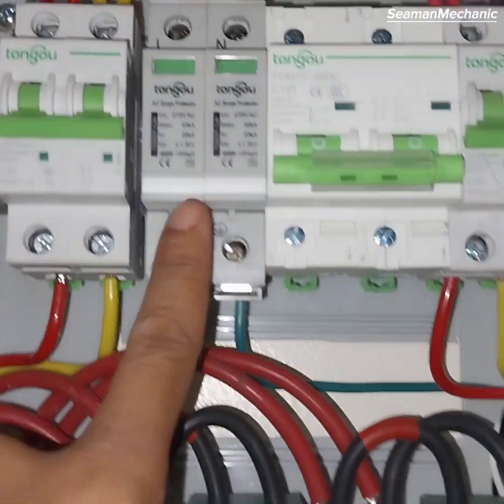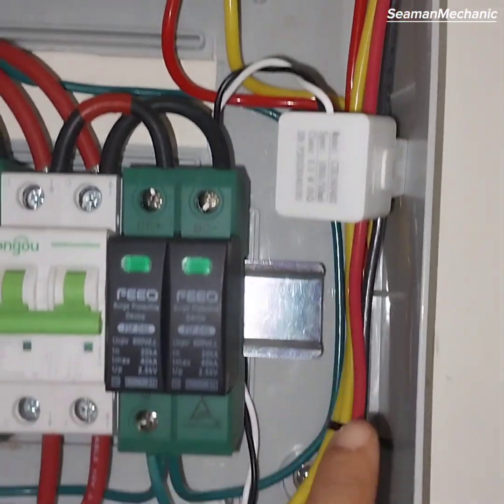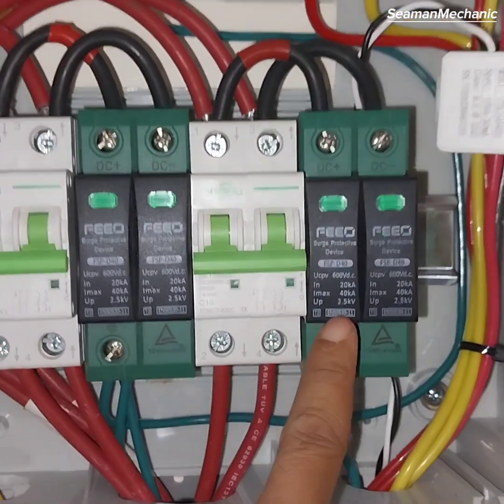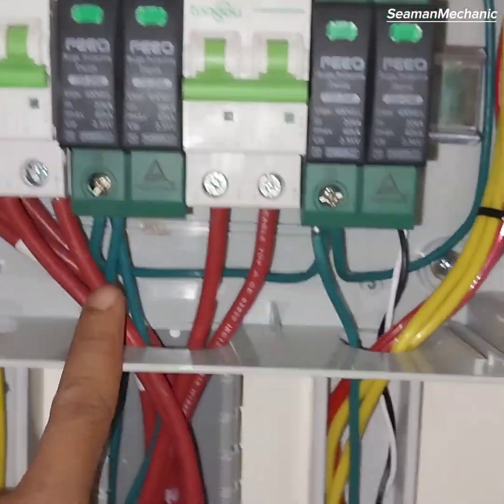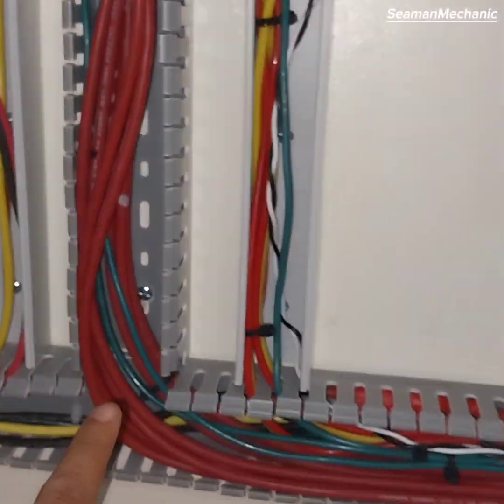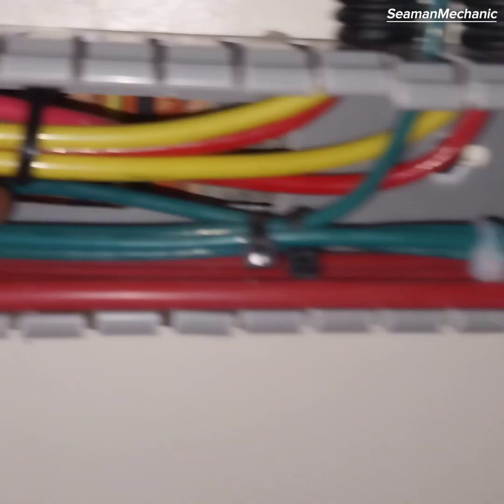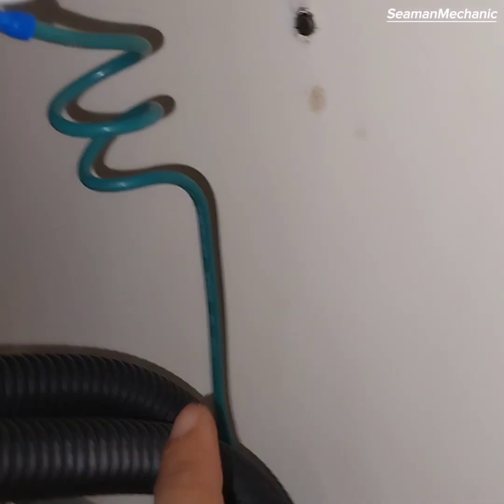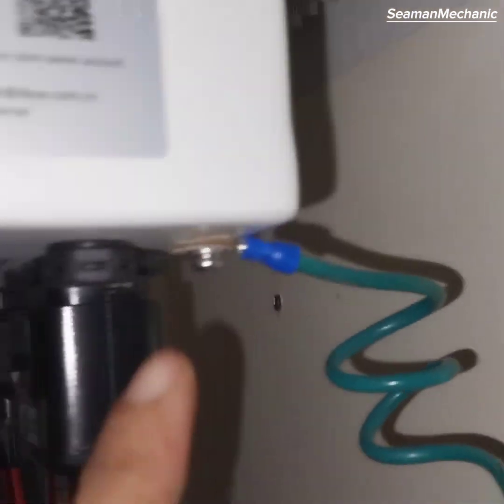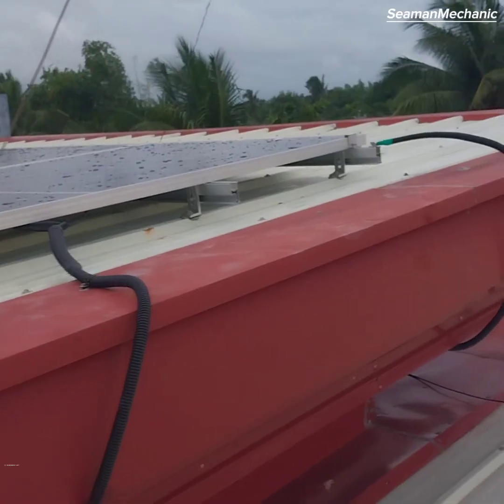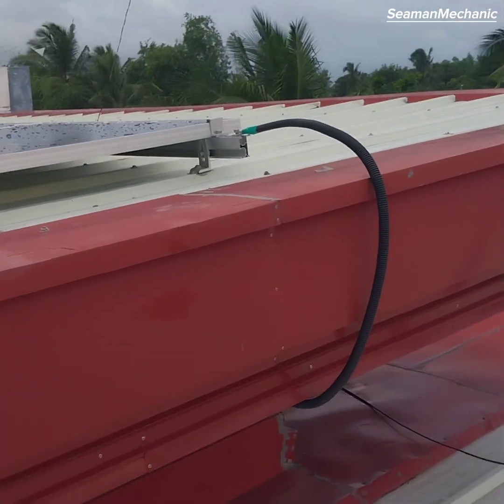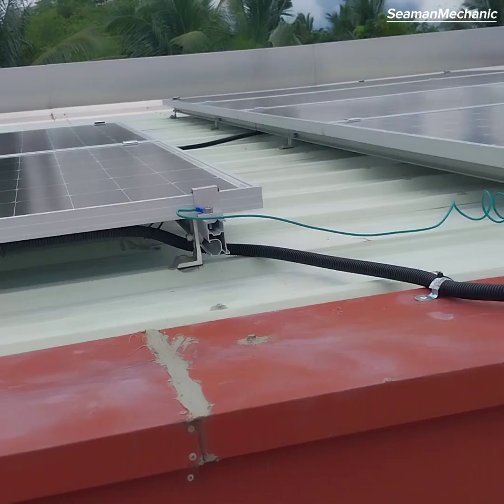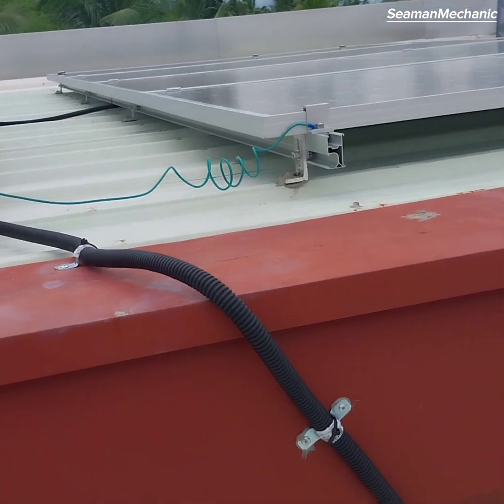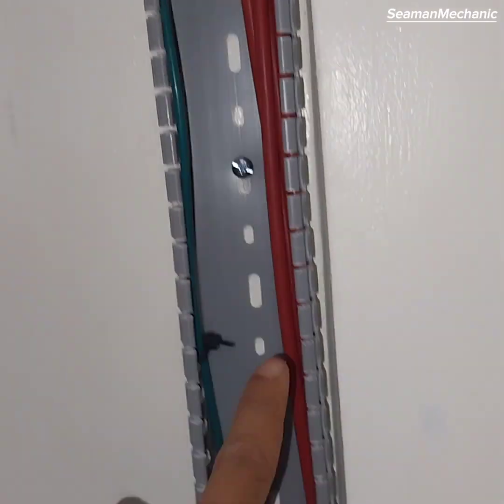Grounding from AC surge protection device is connected to PV1 string and PV2 string surge protection device. Then to inverter. And solar panel mounting structure. Then goes to grounding rod.